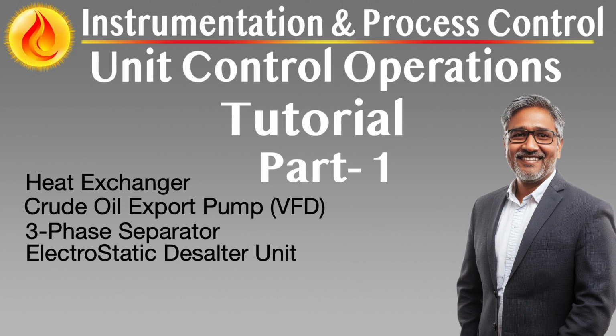Temperature control plays a significant role in desalter performance. Higher crude temperatures reduce viscosity, improve water separation, and reduce emulsion stability. Modern systems incorporate crude preheat control into the desalter logic, adjusting heater duty or steam injection to maintain crude at optimal dewatering temperature, typically in the 120 to 150 degrees Celsius range. Integrated diagnostics ensure that crude does not exceed thresholds that risk vaporization, foaming, or destabilization of downstream heat integration.